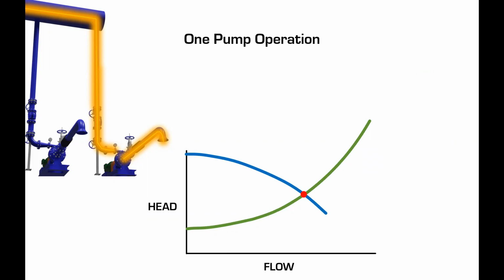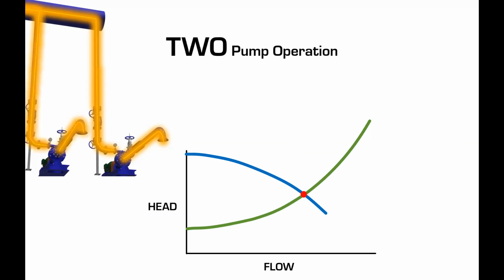And then obviously, we've said this a few times, where the pump curve and the system curve cross is where the pump should operate. What's going to happen when two pumps start? Chris, what do you think is going to happen when two pumps start? I guess that is going to depend on what the system curve ultimately looks like, but we're going to get more flow. You will get more flow. You're right. Two pumps starting will give you more flow. But what's going to happen in the individual sense? What's going to happen to each of the pumps?